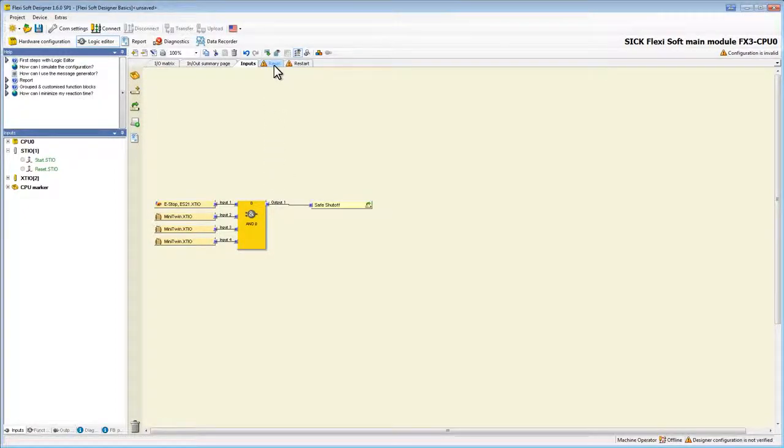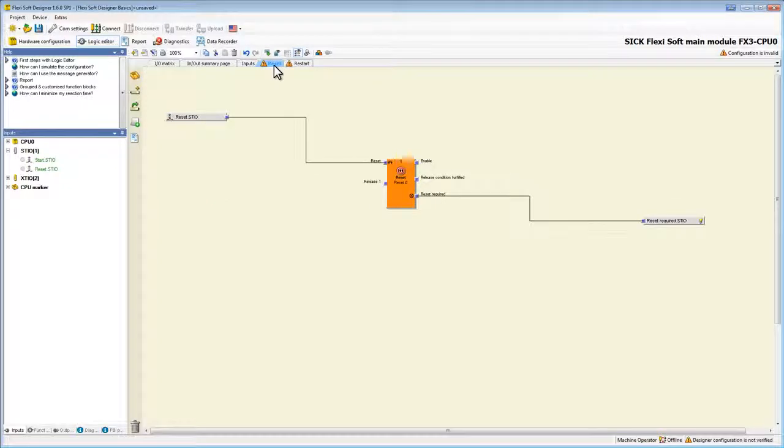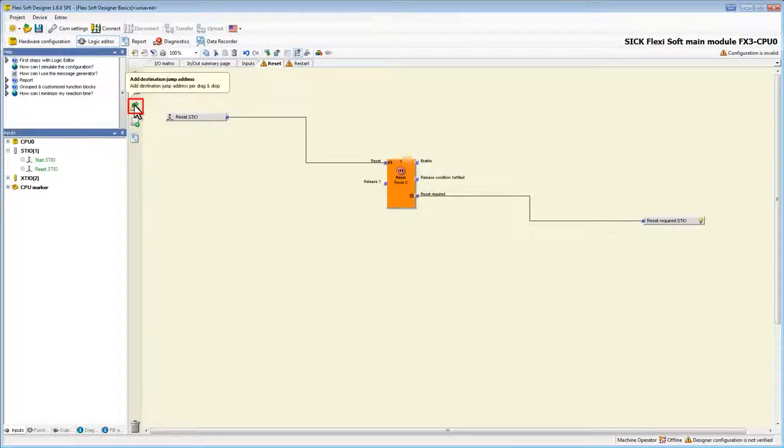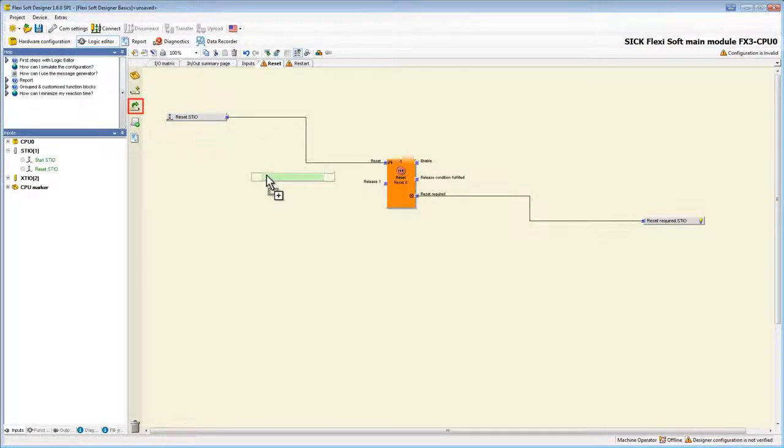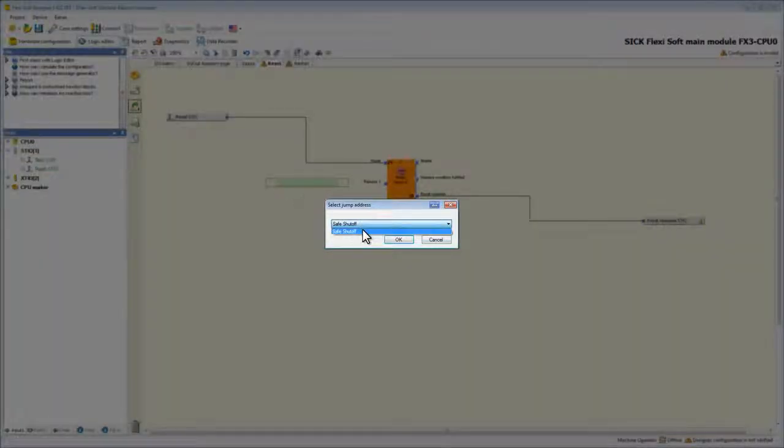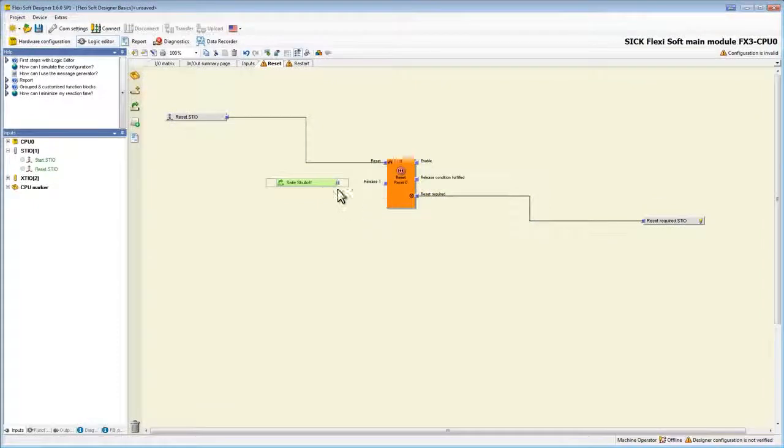On the second page, the reset page, we now need to connect the input of the reset block with our jump address we just created. To do this we drag the add destination jump address to our logic. Again a window shows up and asks us to select the source address. In this drop down menu we will find all available addresses. Choose the safe shut off and click OK.